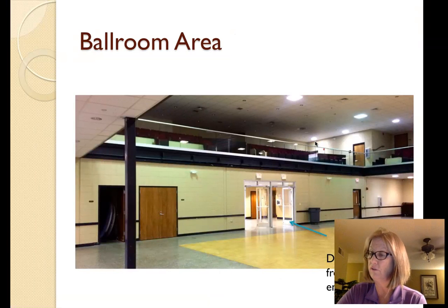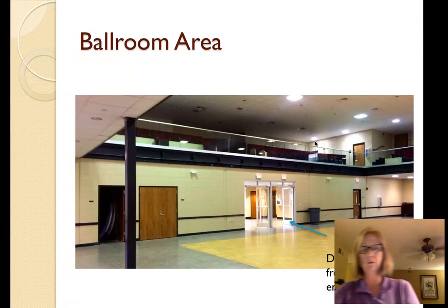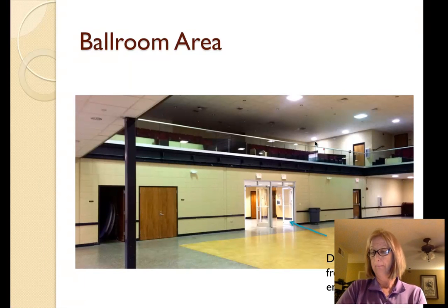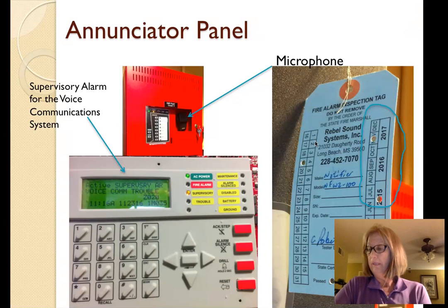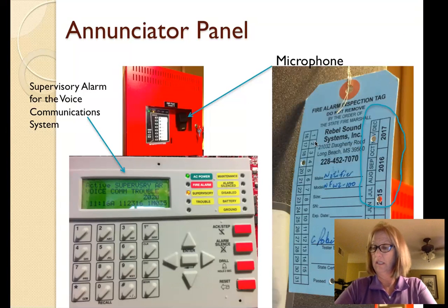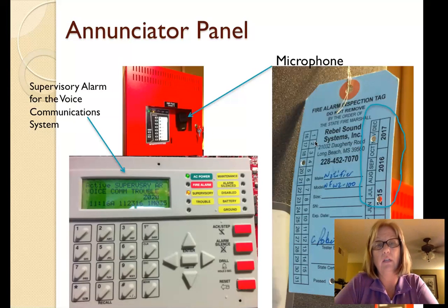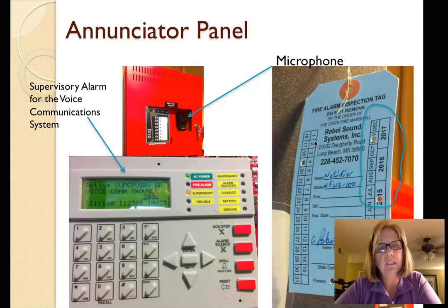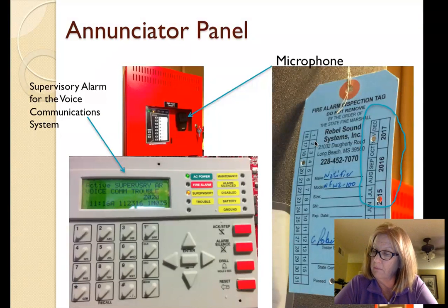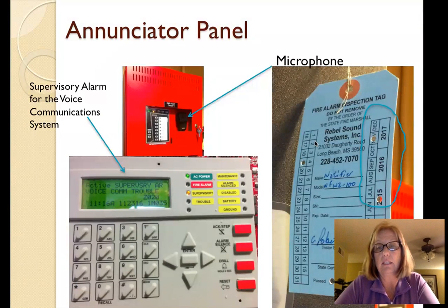The entryway had 2 sets of double doors that opened up onto the ballroom and stage area, as you can see here. The annunciator panel was located in the front entrance foyer area. There was also a manual evacuation system with a microphone in there. It could be used to manually evacuate persons from the building, as well as an automated evacuation system. Unfortunately, we realized that the supervisory alarm for the voice communication systems was showing a supervisory or trouble alarm, and Inspector Ellsworth said he would take care of that immediately.